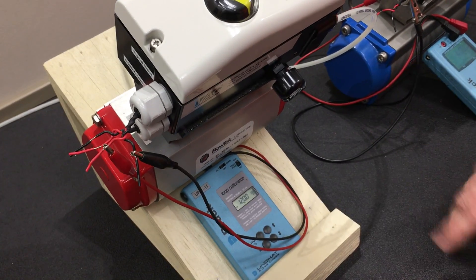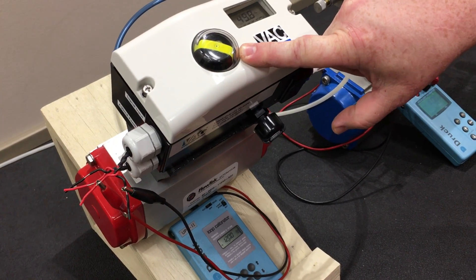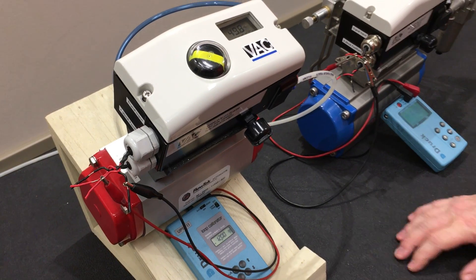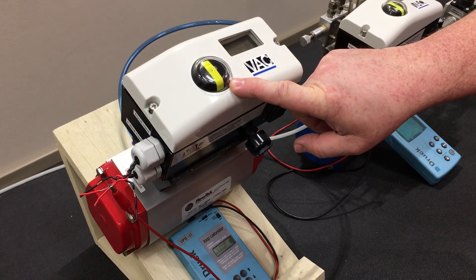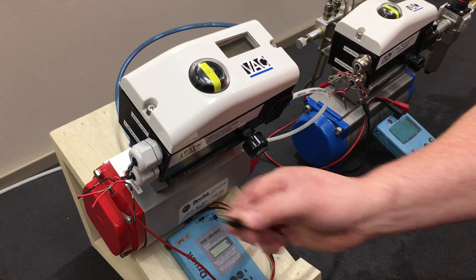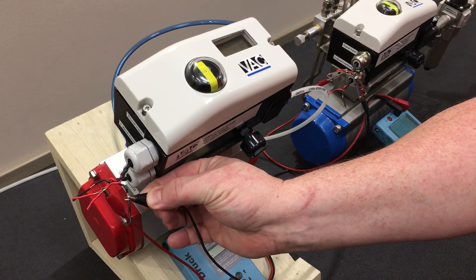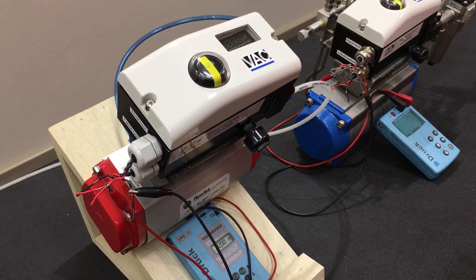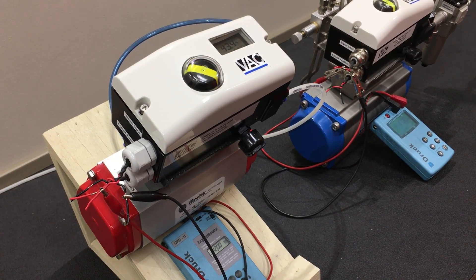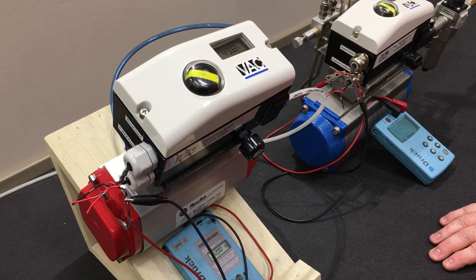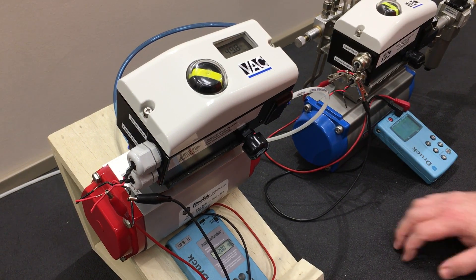We're going to take this unit and run it to 50%, and you'll see that it's now at 50%. We will remove the signal and the unit drives closed. When the signal is introduced back to the positioner, it will go to whatever signal it is given once it boots back up. Back to 50%. That is the function of a standard fail-safe positioner.